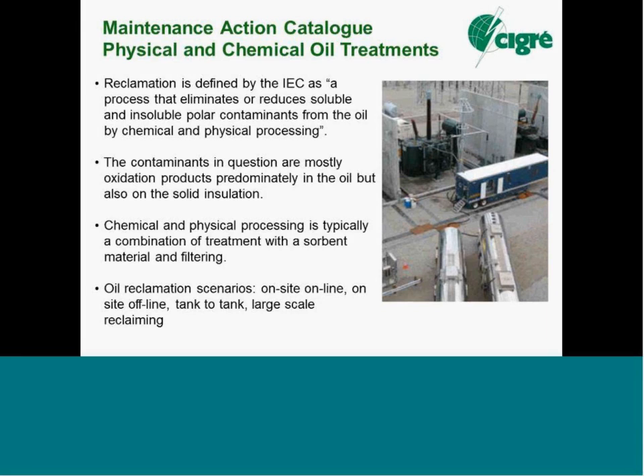Oil reclamation is considered when you have poor oil quality. When oil gets oxidized, it produces acids that will attack the paper, so it's not just heat, but also the oxidized oil and its acids that will lower the degree of polymerization, the indicator we use to show the aging of paper insulation. As the paper ages, its degree of polymerization reduces, and it loses its tensile strength.